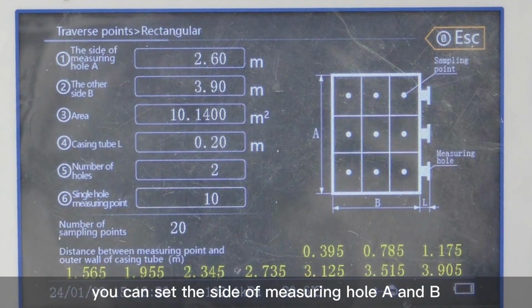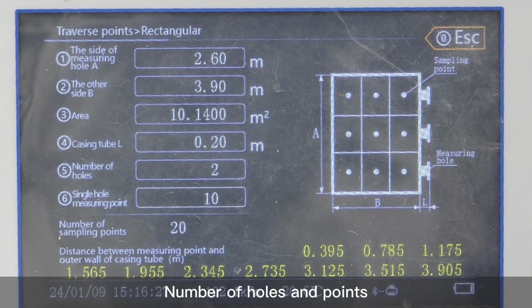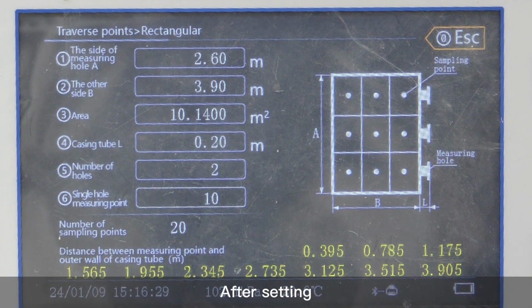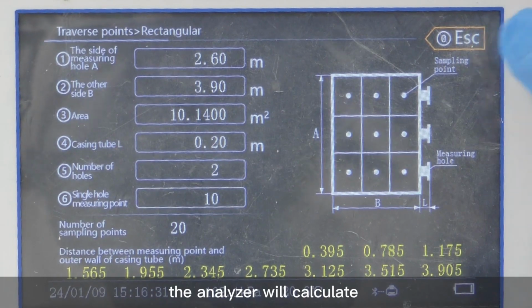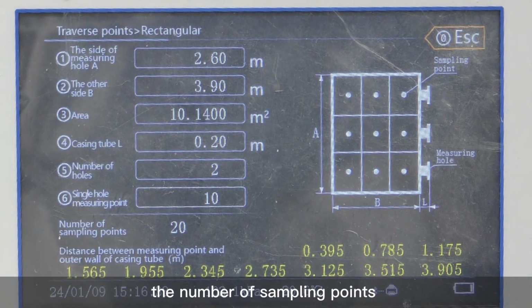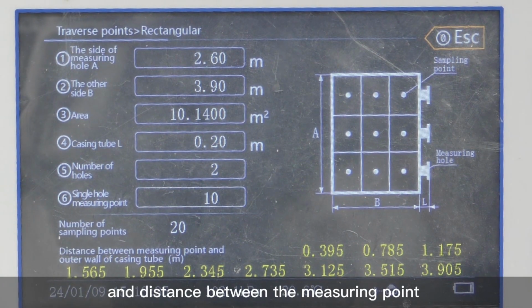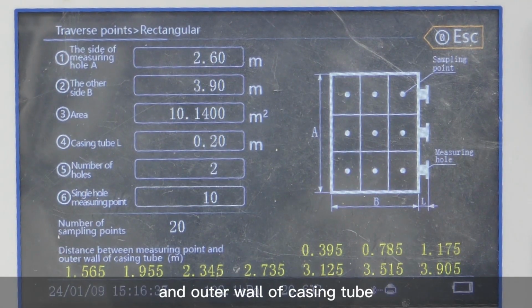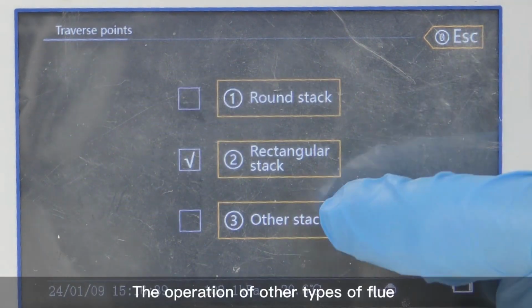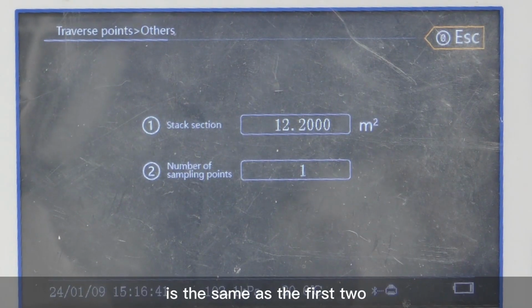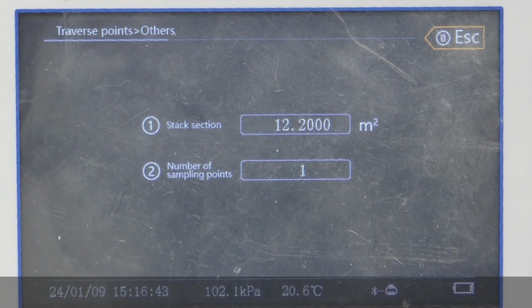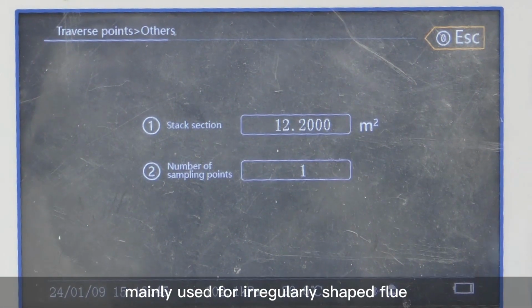Now choose rectangular stack. You can set the side of measuring hole A and B, area, casing L, number of holes and points. After setting, the analyzer will calculate the number of sampling points and distance between the measuring point and outer wall of casing tube. The operation of other types of flue is the same as the first two, mainly used for irregularly shaped flue.